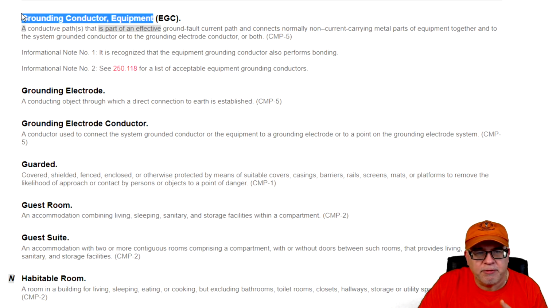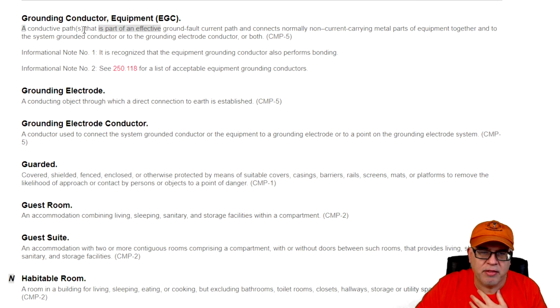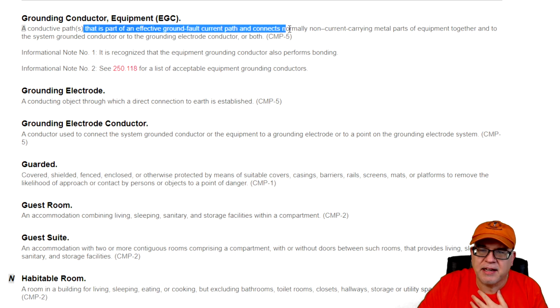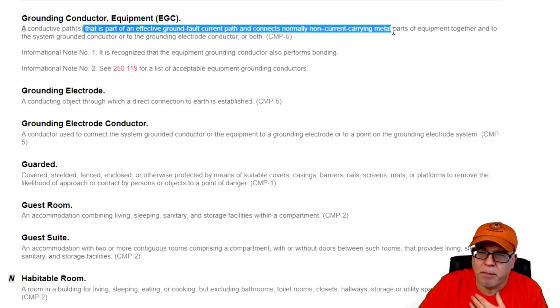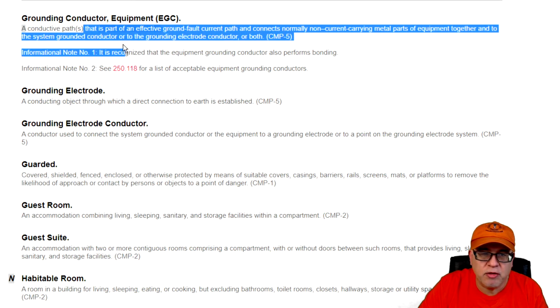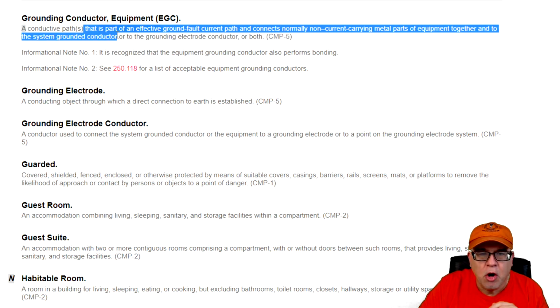Equipment grounding conductor. For years, people have been trying to get this changed to equipment bonding conductor. It ain't happening, okay? We have informational notes that remind people, hey, just relax. If it's an equipment grounding conductor, let's say in a branch circuit, it's also bonding things together. You have equipment bonding jumpers, and we get it. It's okay. So here you see that it is a conductive path or paths that is part of an effective ground fault current path and connects normally non-current-carrying metal parts of equipment together and to the system's grounded conductor, that's back at the service, or to the grounding electrode conductor, or both, okay?